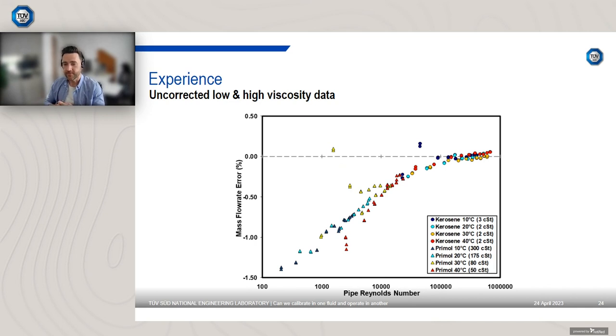Now we have the pipe Reynolds number effect. On the x-axis we have pipe Reynolds number, on the y-axis still mass flow rate error. This is all 8 data sets: kerosene at 10 to 40, Primol at 10 to 40, and you can see there's a clear Reynolds number effect. For high Reynolds numbers, the meter's well within specification and doesn't look overly affected, but as the Reynolds number starts to decrease, there's a clear linear effect. Now, there are a few what look like outliers. They're more likely simply zero effects, which you always have to be mindful of for Coriolis meters.